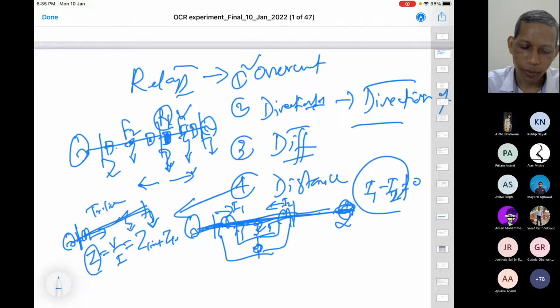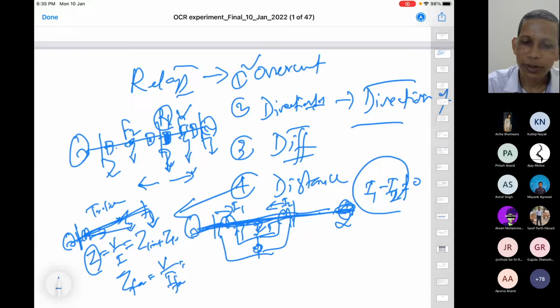But when a fault happens, the impedance path will be nothing but this path. So Z fault will be V divided by I fault, and that will be much smaller than the normal impedance. So what you notice here is that during a fault situation, the impedance seen by the relay, or calculated by the relay, will be much smaller than the normal situation impedance. So this is also indicative of a fault situation. So the point here is why there are different relays: from this you can make a judgment to perform better, to discriminate the faulted path versus the non-fault, sound part of the system. So how can we avoid the fault paths, like in the internal faults?